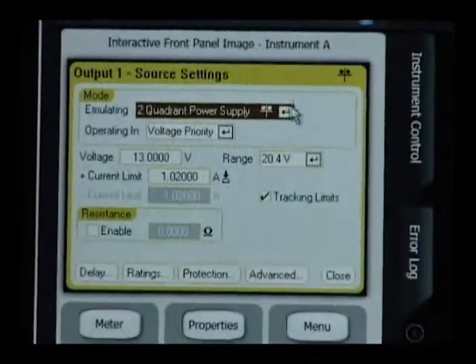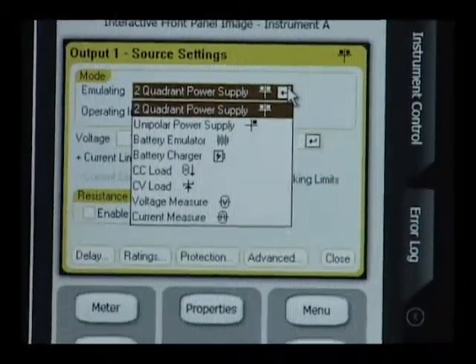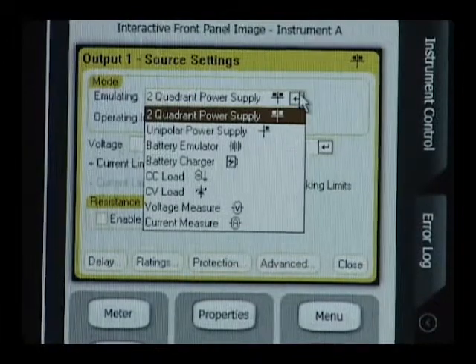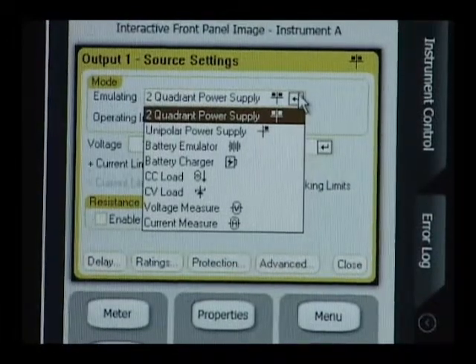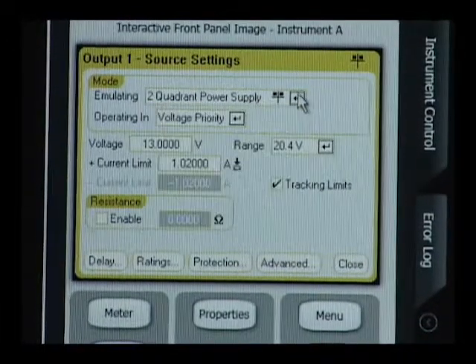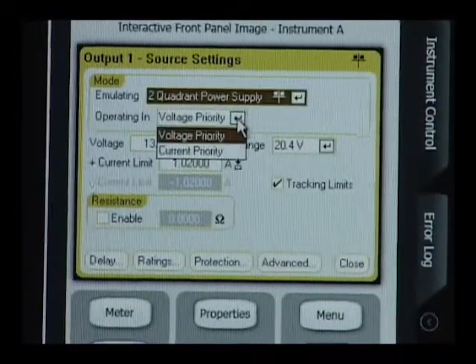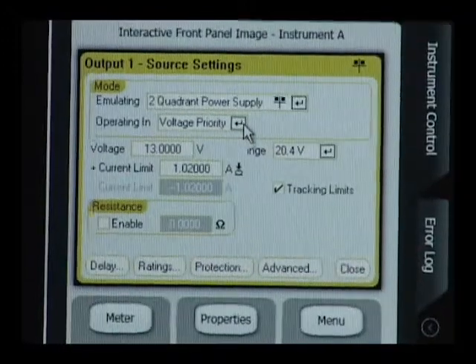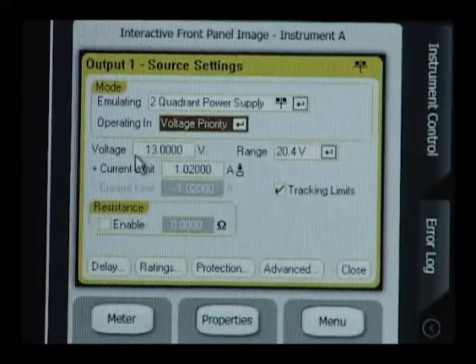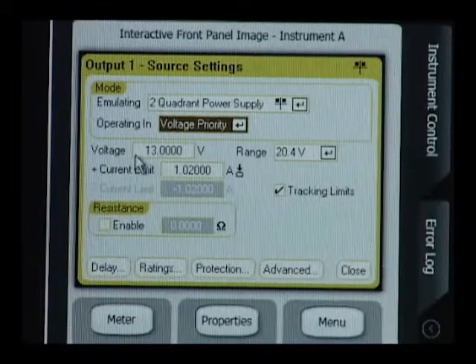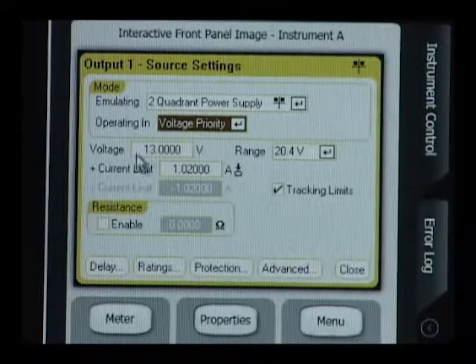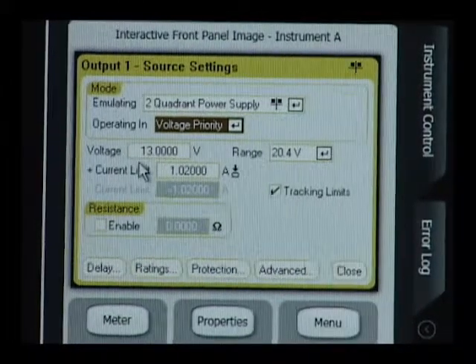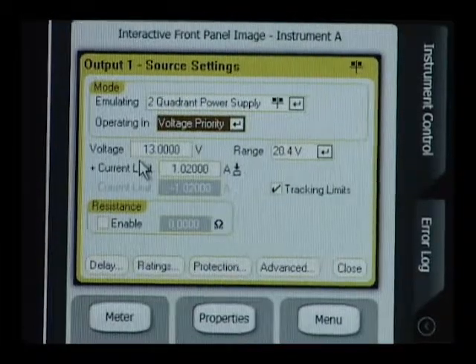Here it's set to be a two-quadrant DC power supply. We have set it for voltage priority because we want a voltage source. And we've set it up for 13 volts output. That's our minimum input line voltage for the regulator as the low line condition.